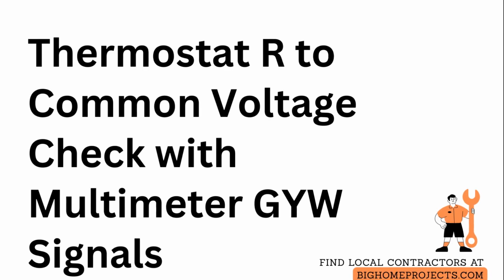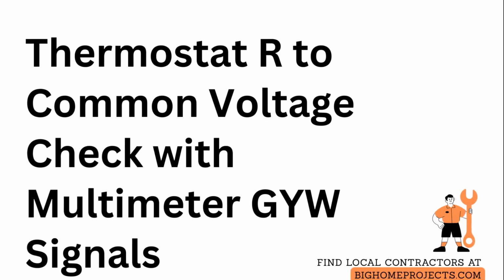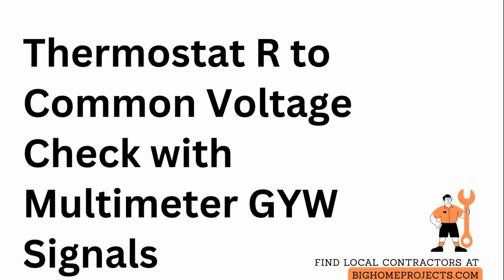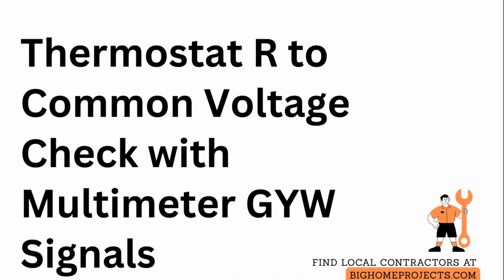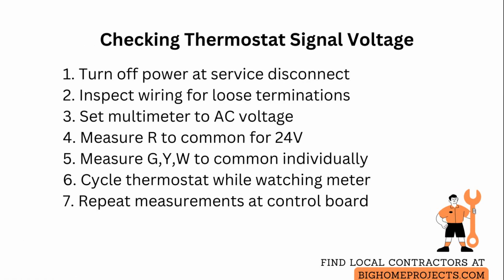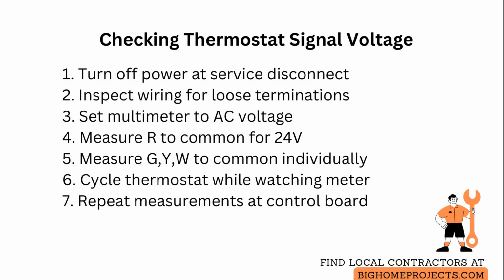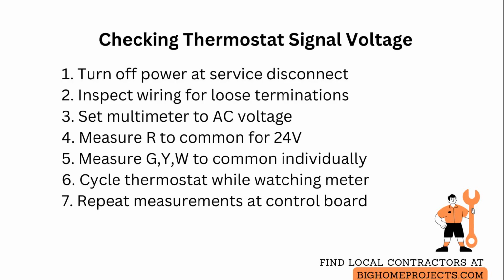Check for proper signal voltage by measuring 24 volts between each control signal terminal and common at both the thermostat and the control board. Start by turning off power at the service disconnect. Remove the thermostat cover and mount, and visually inspect wiring for loose or corroded terminations.